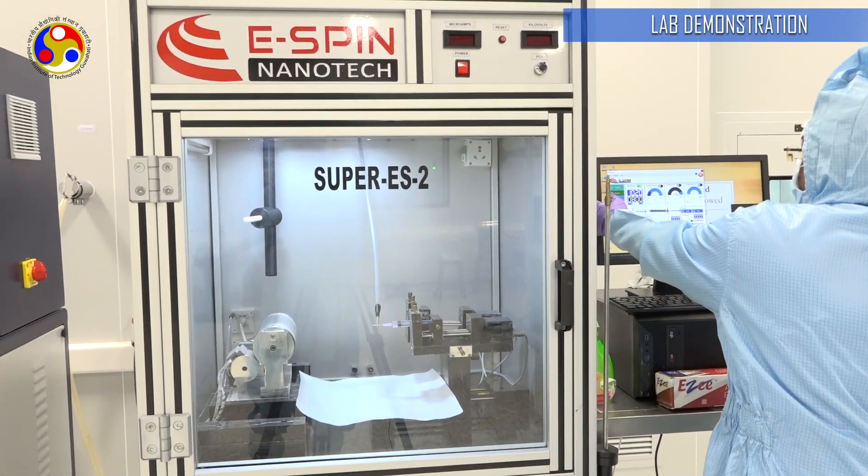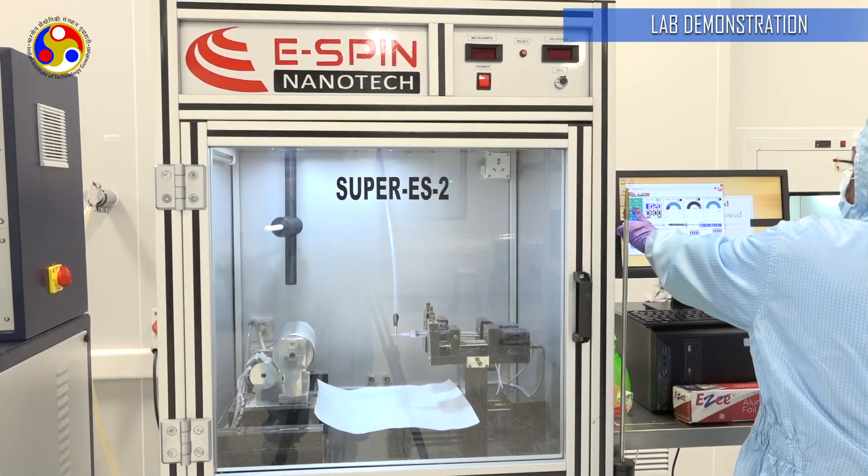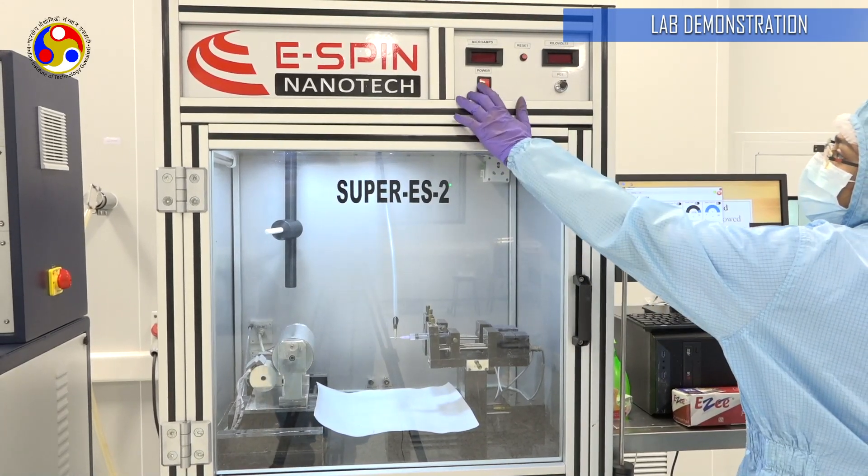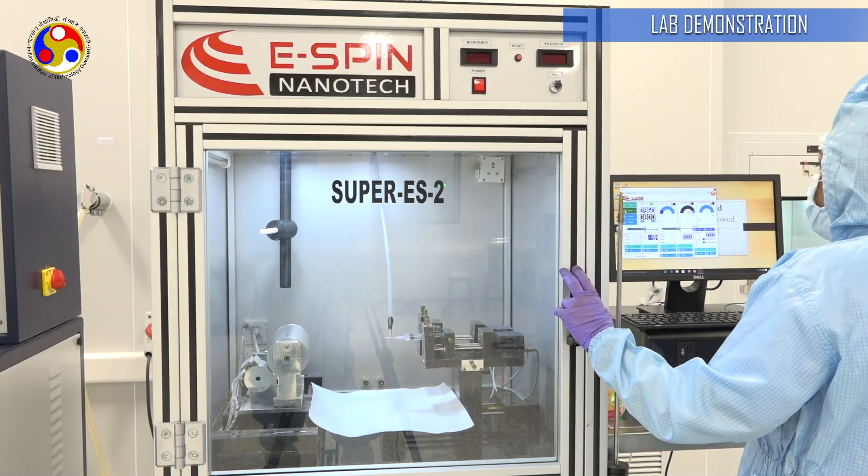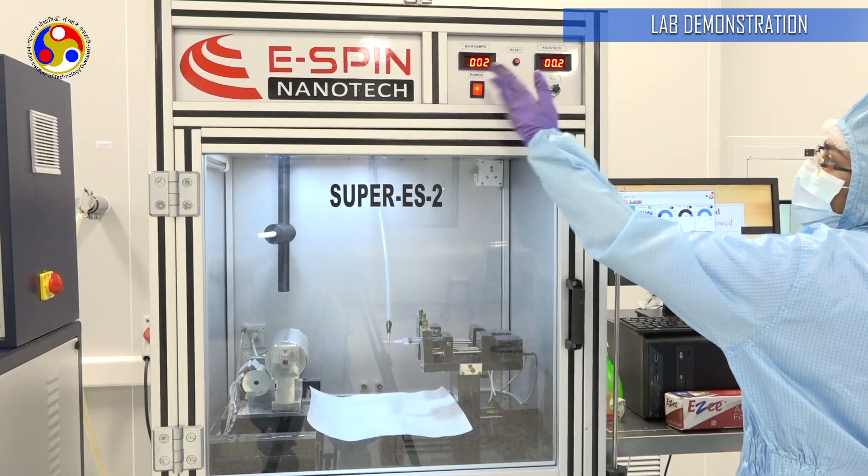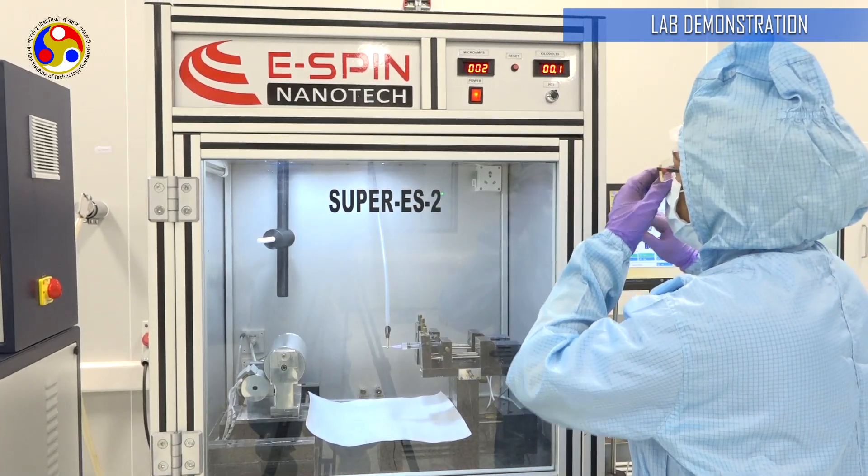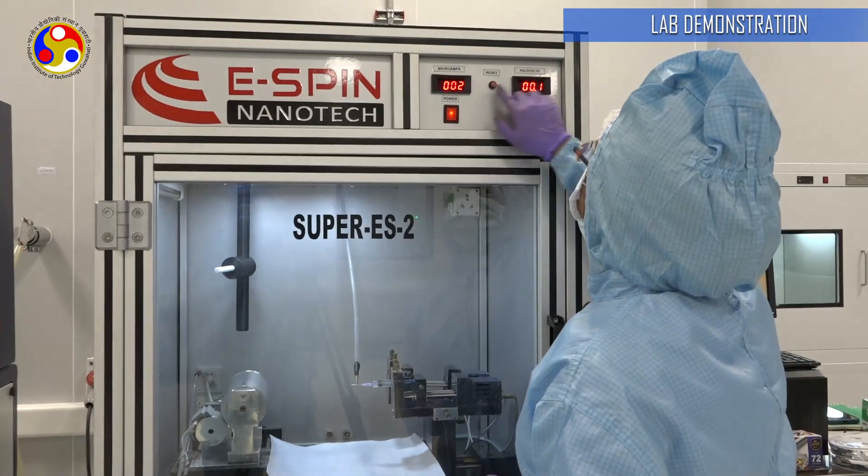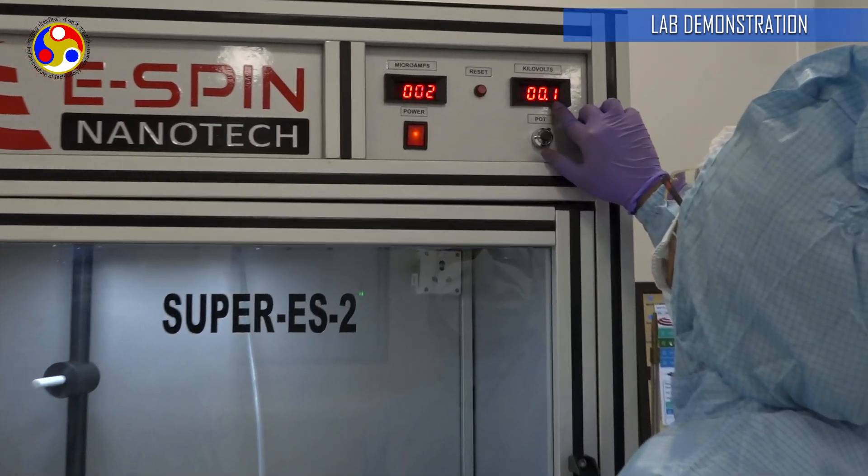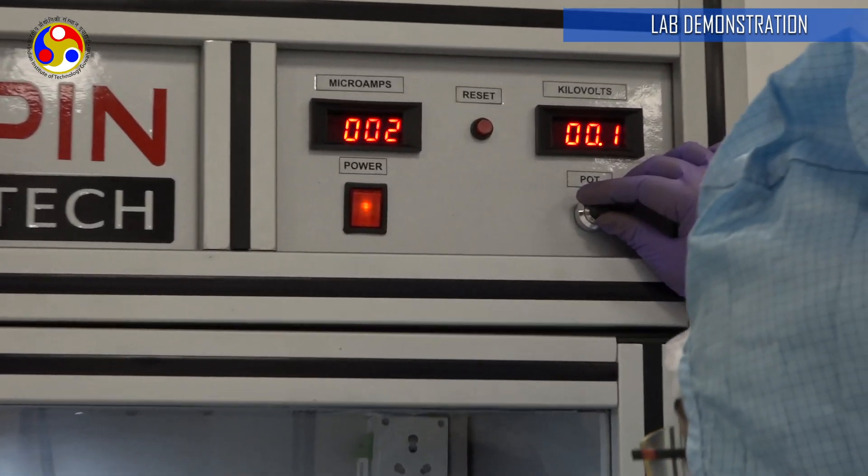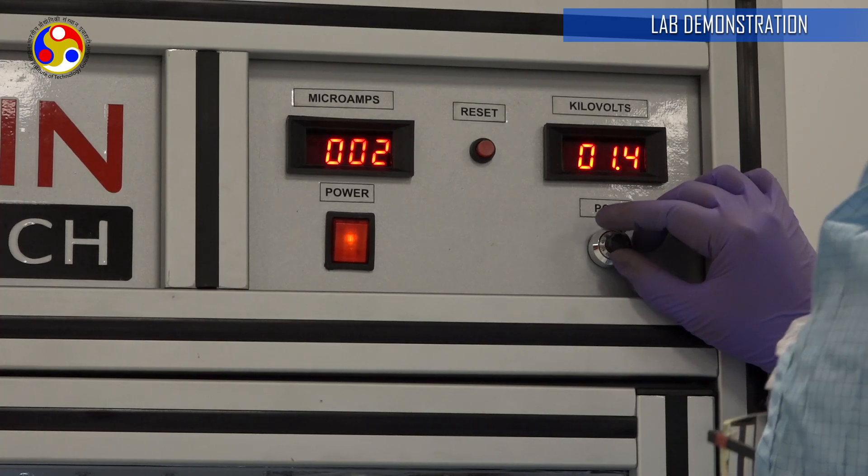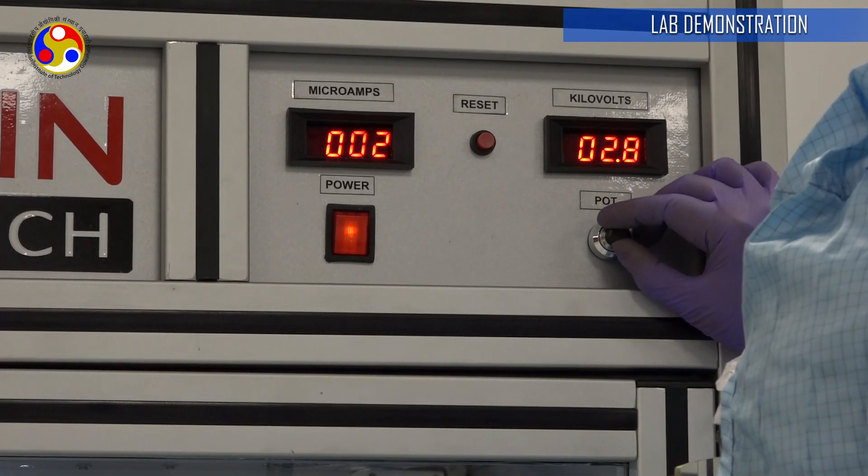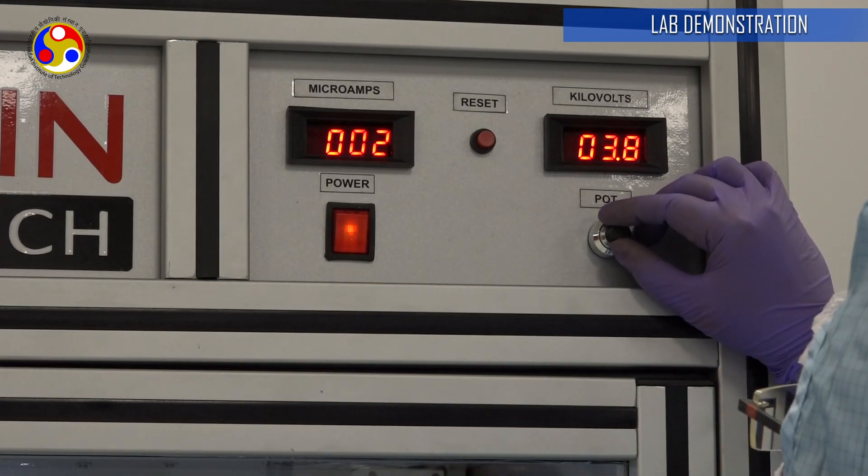I am going to turn it off again and show you what happens. Since the HV is off, this switch won't work. Nothing is showing here, but now that I am turned HV on, the power comes on. It's at 0.1 kilovolts. I am going to start slowly increasing, very slowly, till my desired value is reached.